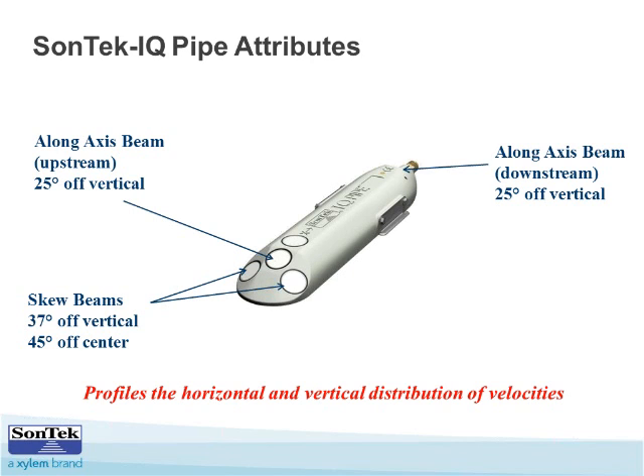Just to review some of the features in detail, as you can see here, we have, as some of our older instruments do, and the IQ Plus and Standard do, these centerline beams, one looking upstream, one looking downstream. But in addition to these, so this gives you your centerline velocity, but we also have these skew beams, one that looks out to the right of the pipe and one that looks out to the left, pointing forward. So as we say, we're getting a horizontal distribution of velocity, and we're getting this vertical distribution of velocity. Again, it's not velocity, it's a full velocity profile in cell sizes down to 2 centimeters.